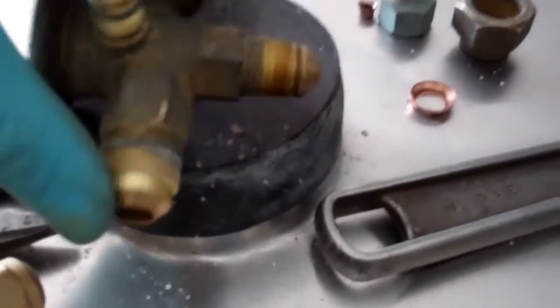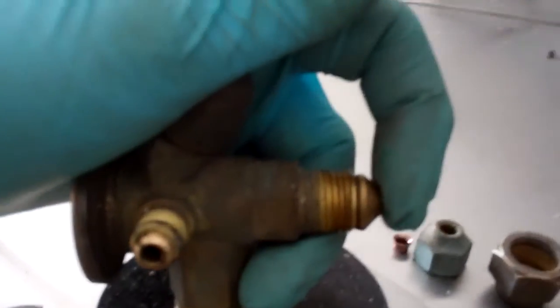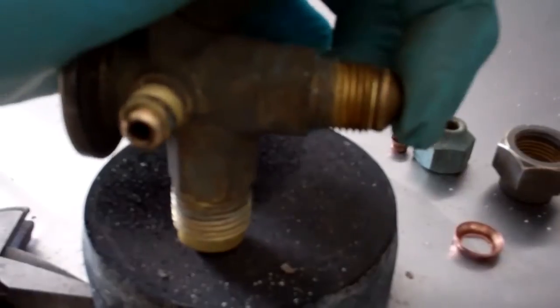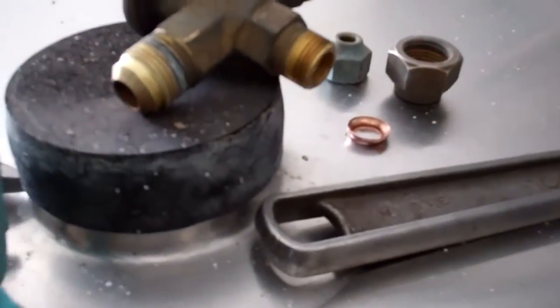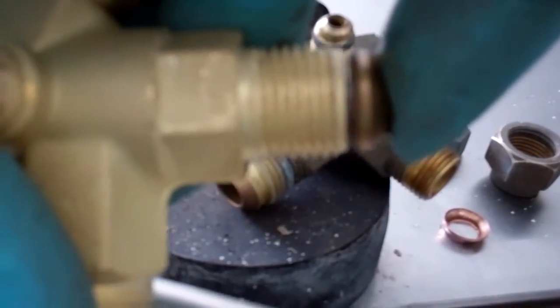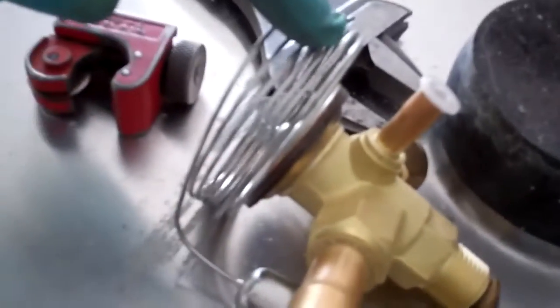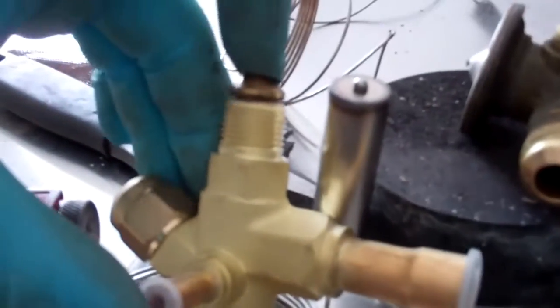Got the old flares cut off, point cleaned up. That's the old valve - that's solid, there's no movement. There should be a couple of millimetres of spring pressure there - try that in a new one. That movement there is used with pressure in the bellows and the little points, so when you get one of these that's leaked out, that's one of the symptoms. You can take it apart and still check.